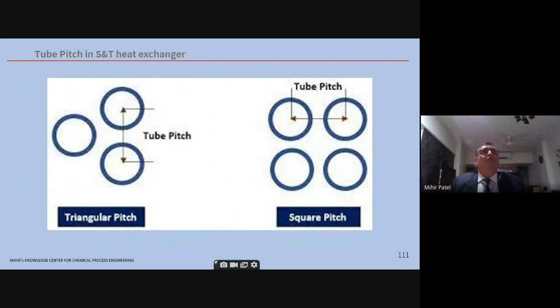Tube pitch. So again, the tube pitch I've shown, triangular tube pitch, and on the right side you see the square tube pitch. Normally tube pitch is kept at 1.25 times to 1.5 times the outside diameter. So 1.25 to 1.5 is the range of the tube pitch.